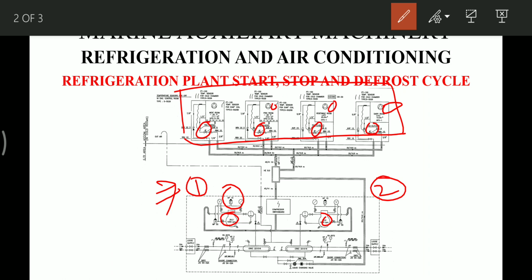After this, the electric heating elements in the freezing room are switched on. As long as the coolers are covered with ice, the melting takes place and all the heat is taken away, and the temperature of the cooler and the refrigerant is constantly kept near zero, because while ice is present, the temperature won't increase.